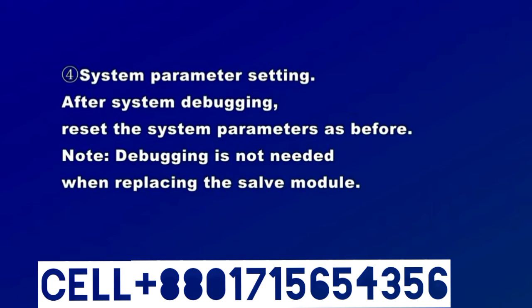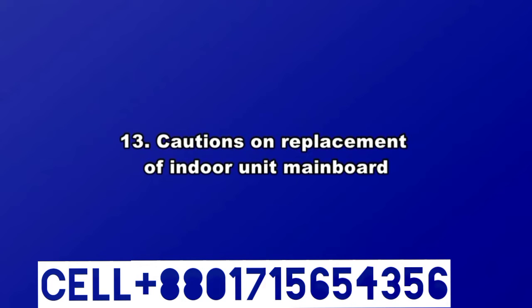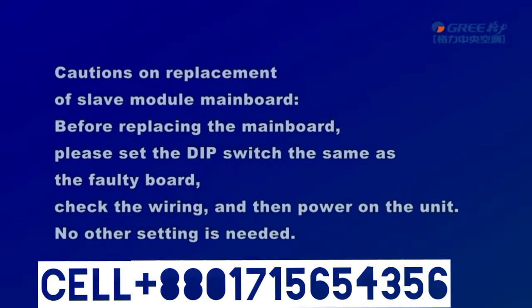4. System parameter setting. After system debugging, reset the system parameters as before. Note, debugging is not needed when replacing the slave module. 13. Cautions on replacement of indoor unit mainboard. Cautions on replacement of slave module mainboard. Before replacing the mainboard, please set the DIP switch the same as the faulty board. Check the wiring and then power on the unit. No other setting is needed.